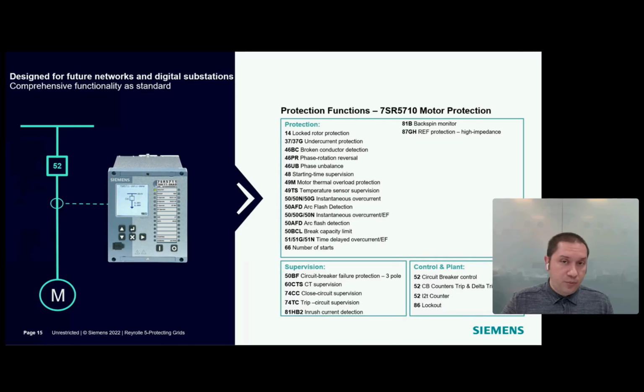Thermal algorithms are important here. Thermal algorithms are optimized to closely match the thermal characteristics of motors. 49M, motor thermal overload protection, has operation curves of the thermal algorithm. The calculation considers effective present loading and prior loading and unbalanced currents on the motor operating temperature. Starting and cooling constants modify the thermal characteristics during motor run-up and stopped conditions. And also, a user-definable thermal curve is selectable to allow matching of the relay thermal characteristic to all motor and cooling system types.